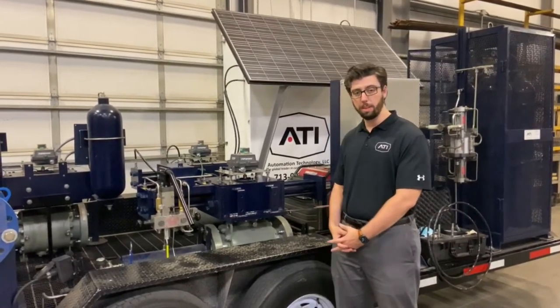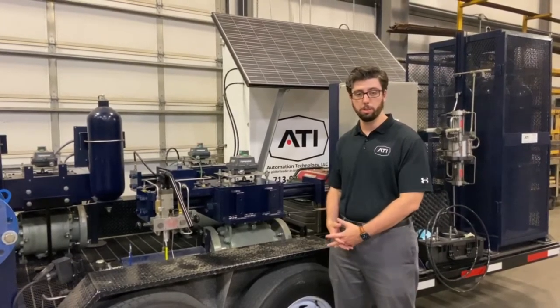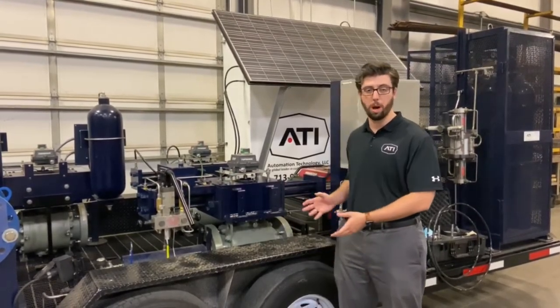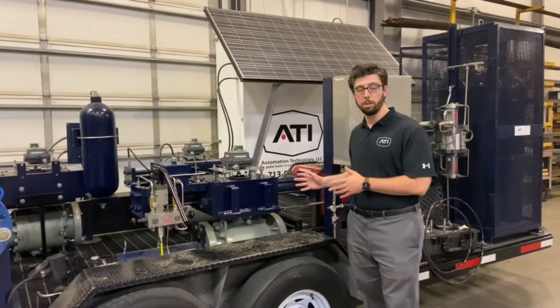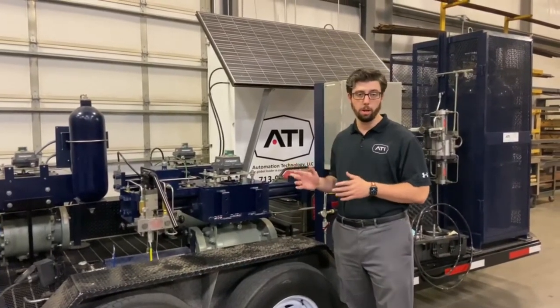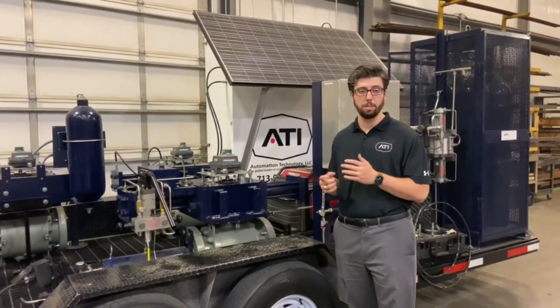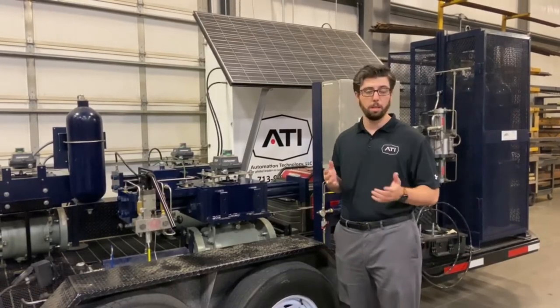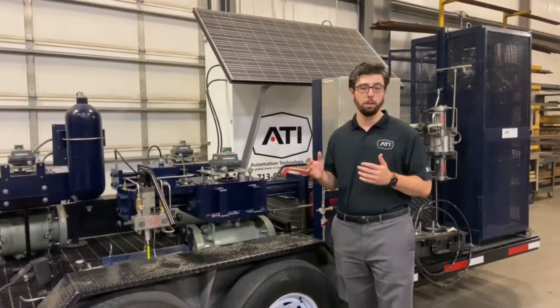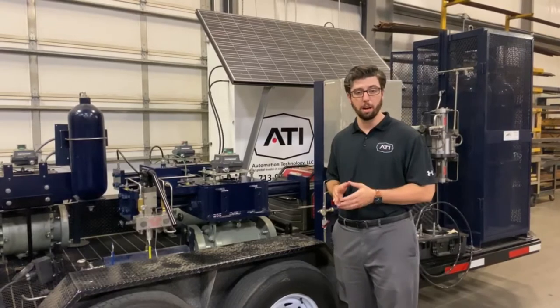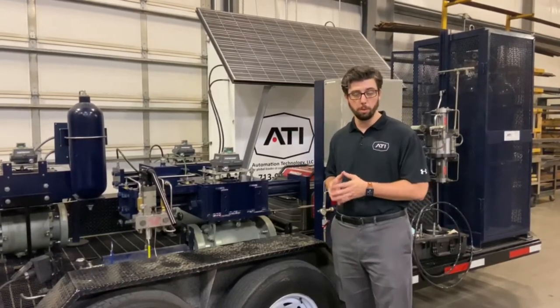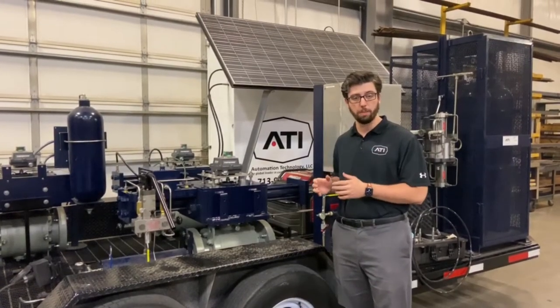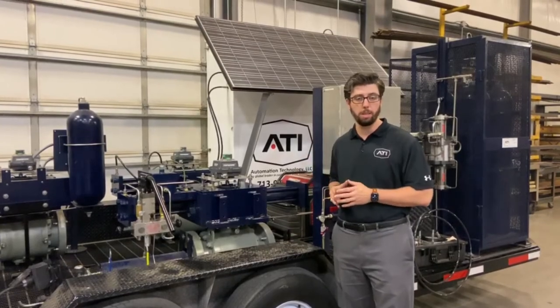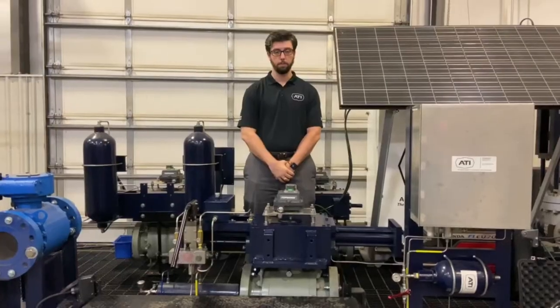And this specifically is our quarter turn direct gas actuator with a few options. The quarter turn direct gas is for applications such as natural gas pipelines in remote areas where power and instrument air is not easily accessible. We can take the natural gas straight off the pipeline and use that to actuate the valve.